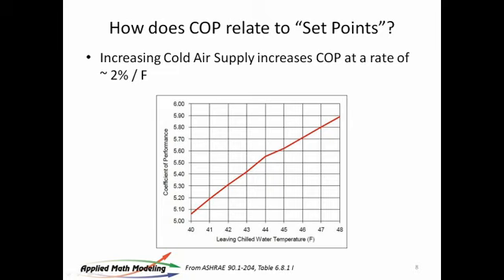So here's a chart. This is from the standard ASHRAE manual on data center efficiency, that shows that by increasing the cold air supply temperature, the COP improves. And that was my point I just made in the chart, that by driving up the supply air temperature, you get an improvement in the overall efficiency of the system, meaning the COP goes up, and it goes up at a rate of approximately 2% per degree F. It's actually 3.5% for every 1.8 F, so it rounds out to about 2% energy efficiency improvement by increasing the cold air supply temperature. So you want in your data center to try to drive the supply air temp up as high as you possibly can to save energy. That's what that's telling you.